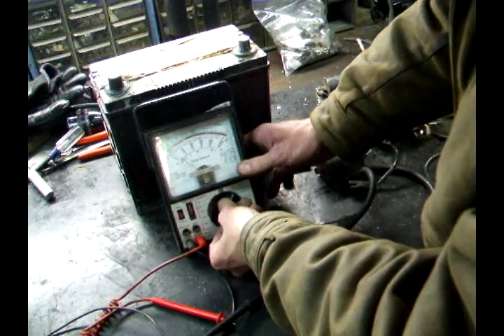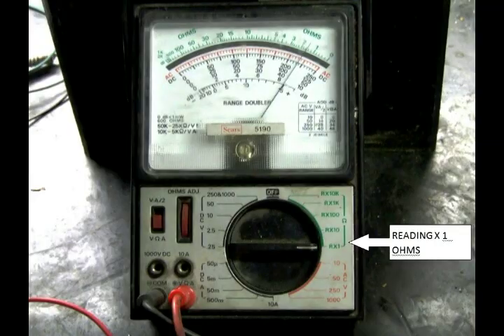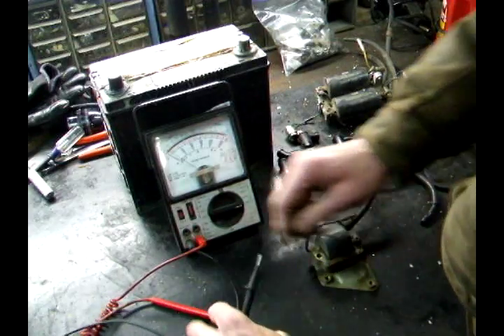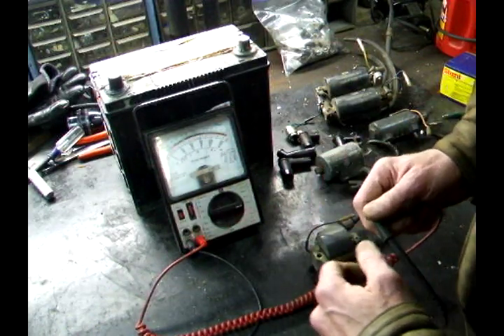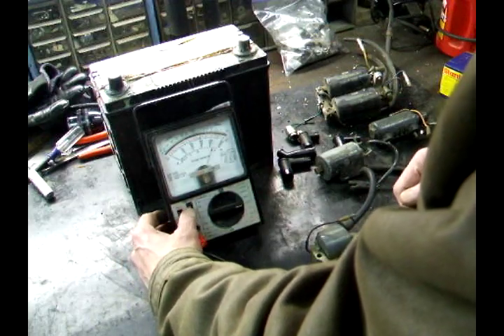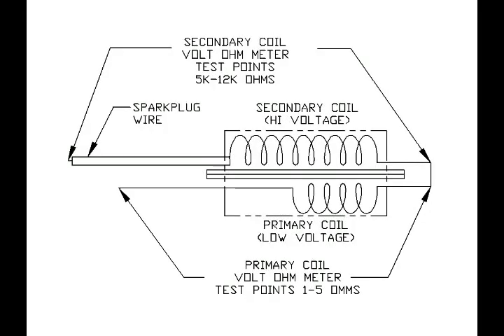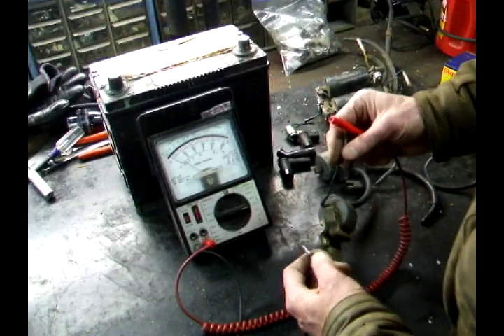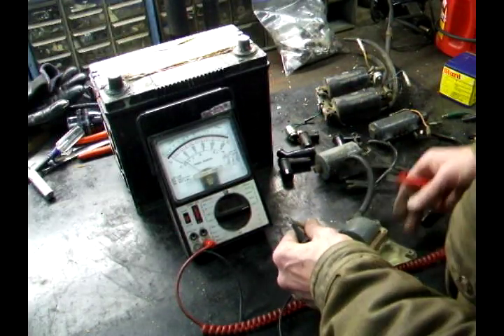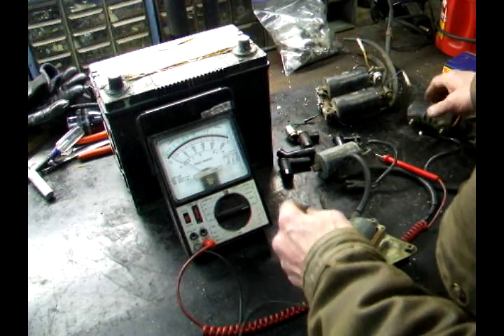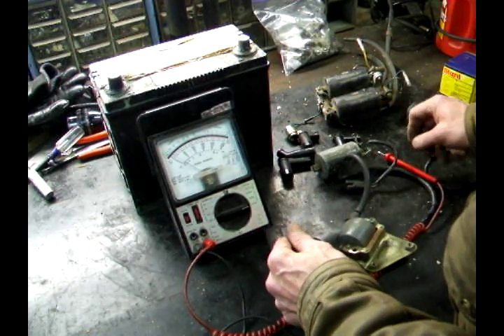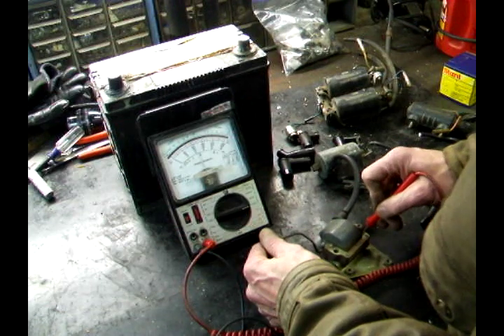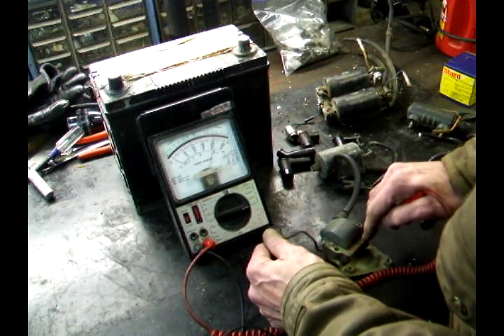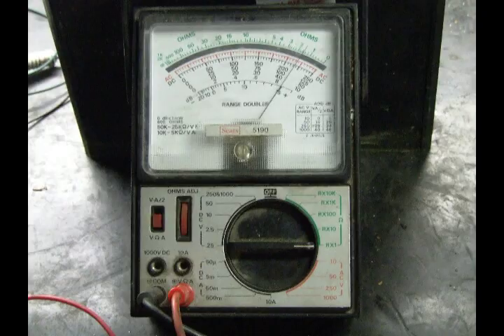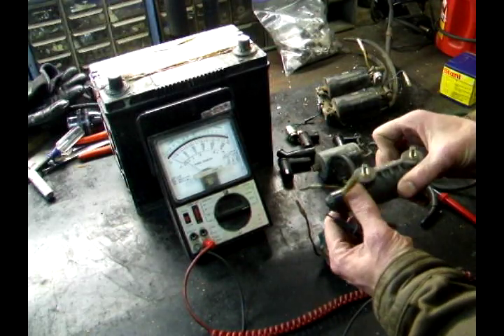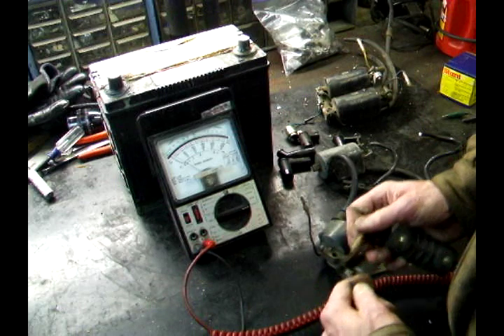Set your Volt Ohm Meter to the R times 1 range. Test your meter and zero it. Take the wire, usually a black wire or a colored wire like on this one. You want to measure across that either to the ground if you have this style. See, I got about 1 ohm. Or if it's this style where you have 2 wires, you want to measure across the 2 wires.